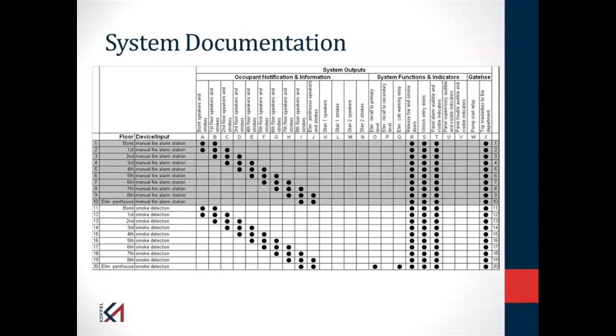I don't know how I'd test your system without this, because I don't know what that smoke detector is supposed to do. This is something the design professional would have put together and the installing contractor would have updated, and it's what the contractor uses to program your fire alarm system. Hopefully you have this sequence of operations matrix, or documentation like it. NFPA 72 does a better job than some other standards here; it specifically says that a record of completion, which tells me all kinds of things about your system, should be stored at your fire alarm control unit in a cabinet marked fire alarm documents, so I'd have that matrix available when testing your system. Here are some examples of what those might look like.